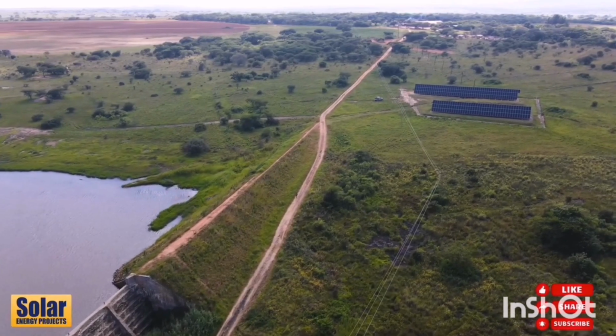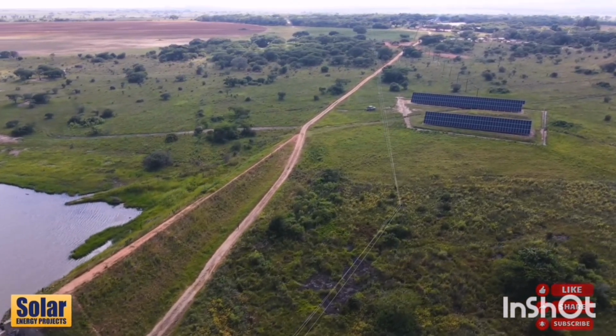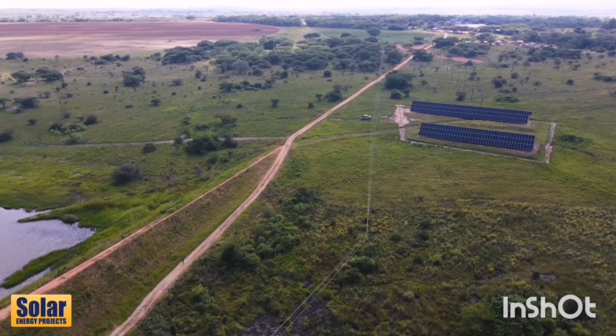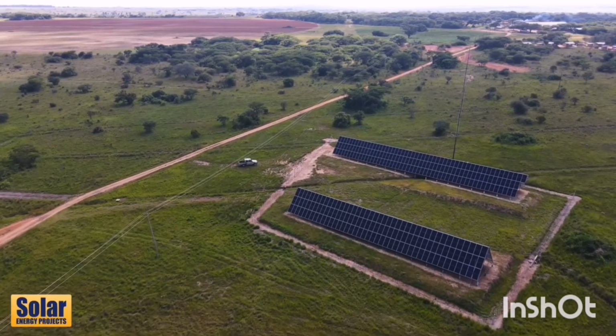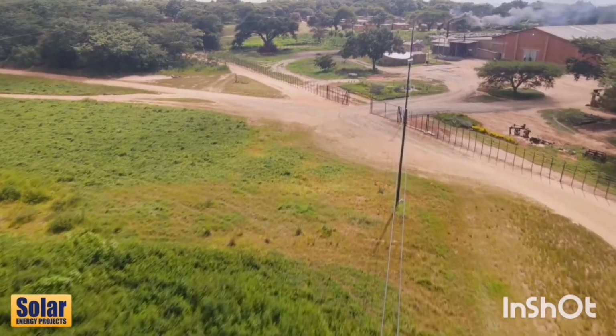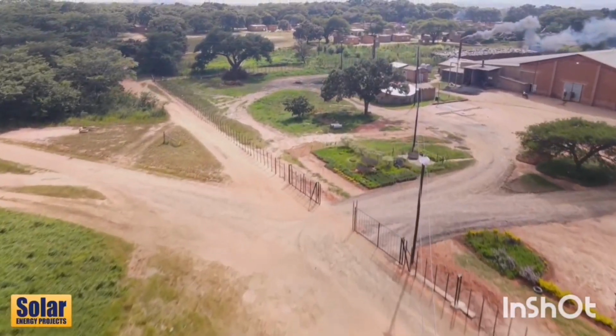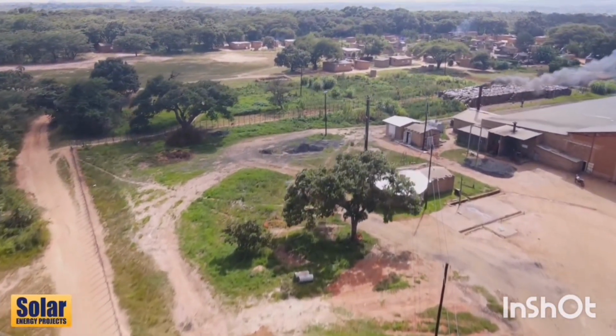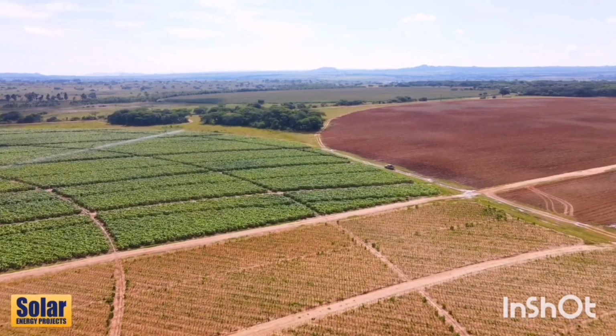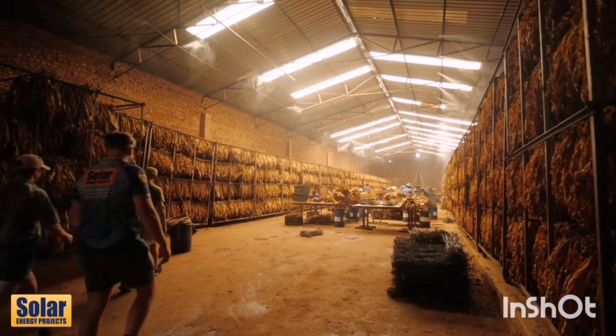I'd like to introduce you to our phase 2 solar project, the second phase of our 3-phase rollout of the solar option. In order to utilize that energy to run the second phase, which is our barns, homestead, borehole, etc., we've run a DC line from the solar array up to the central point here by the transformer and our generators, and we've put in a 100 kVA inverter and a battery system which enables us to use that power either for pumping or for running our barn and homestead setup.